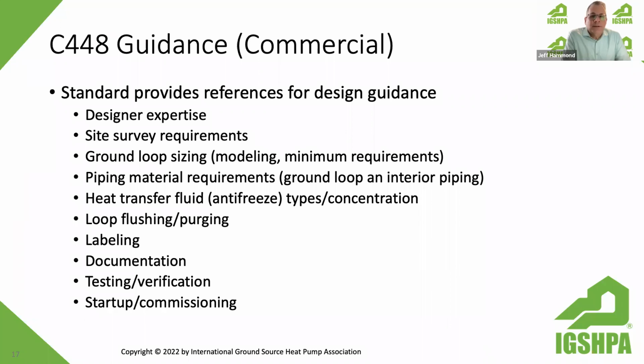Piping material requirements—I mentioned that earlier. We don't want to put PVC in the ground, for example, but the interior piping can be different, so it specifies what's acceptable and what's not. Same with antifreeze and concentration, flushing, labeling of the piping, documentation that should be delivered to the end user or building owner, testing, verification, and a big, very important part: startup and commissioning.